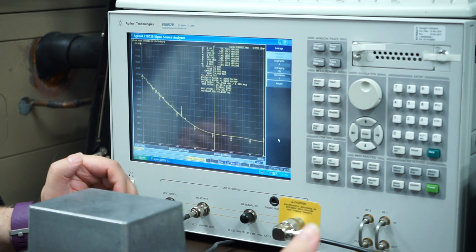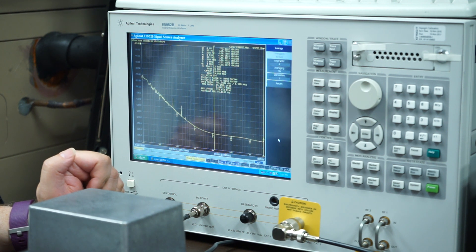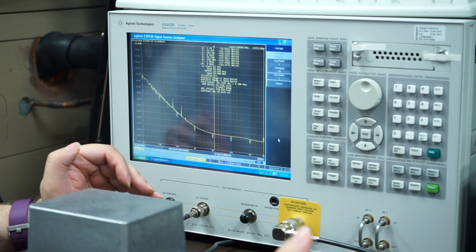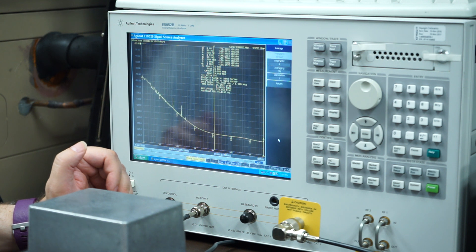So it's not only important to have good instrumentation, but to know the proper setup and usage of the instrumentation. Again, we do good isolation on power supply cables, an isolated grounded RF box, very good isolation, anti-static matting underneath the test and measurement device.